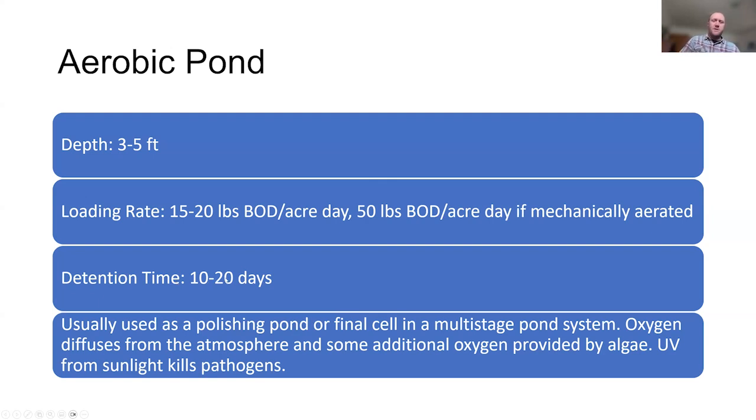They're often used as polishing. We'll go over this in a minute, but in a series, you might have an aerobic pond at the end, or you could even have it after another wastewater treatment method to get that last bit of treatment to meet your discharge limits if you are having a hard time meeting those goals. And because they're so shallow, UV does kill some of the pathogens as the water leaves the lagoon too.